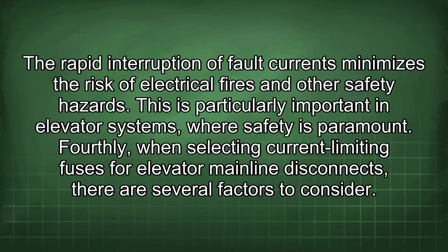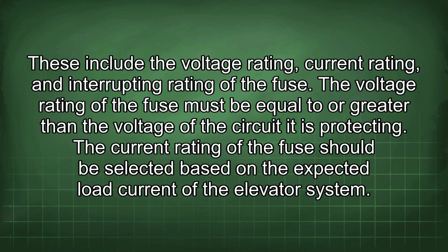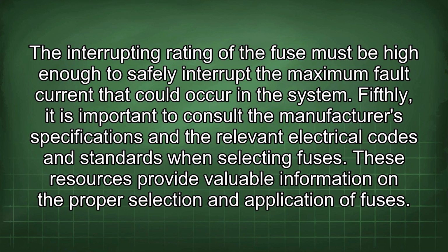Fourthly, when selecting current-limiting fuses for elevator mainline disconnects, there are several factors to consider. These include the voltage rating, current rating, and interrupting rating of the fuse. The voltage rating of the fuse must be equal to or greater than the voltage of the circuit it is protecting. The current rating of the fuse should be selected based on the expected load current of the elevator system. The interrupting rating of the fuse must be high enough to safely interrupt the maximum fault current that could occur in the system.